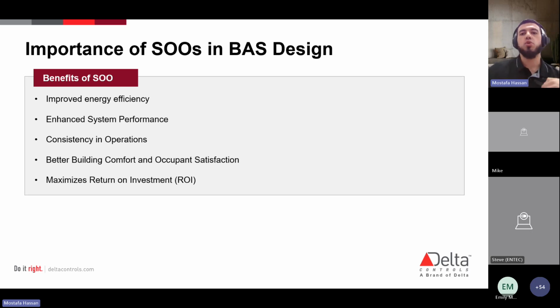So the sequence of operation also ensures that all systems are going to operate as intended, right? As clearly outlined by the control logic, the schedules, the system responses to various conditions. This is going to help them maintain optimal performance, and it's going to reduce wear and tear. So it's going to extend the life of the equipment, right? Having a proper sequence of operation, right?